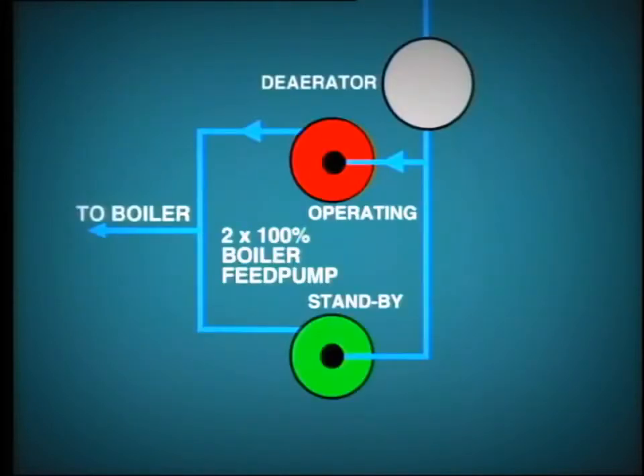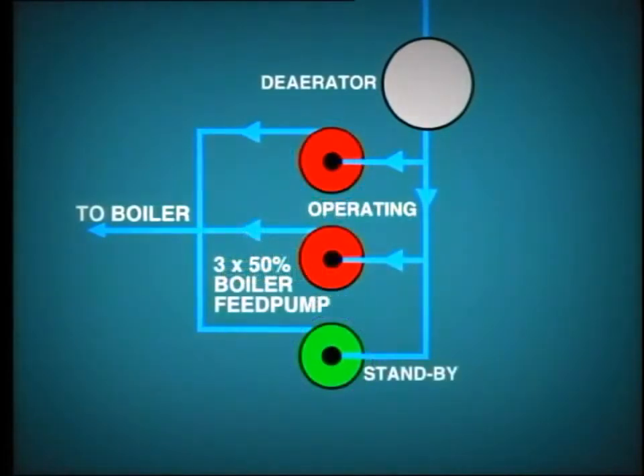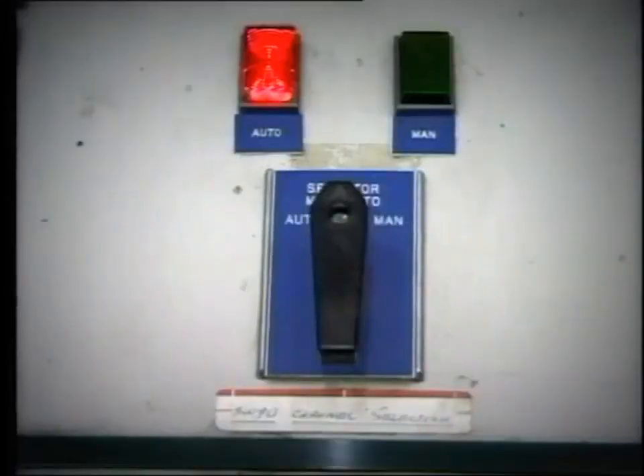In many power plants, two boiler feedwater pumps may be installed, providing 100% standby. An alternative to this arrangement is to provide three 50% pumps. The standby pump may be made available for automatic start in case of failure of the running pump and a decrease in feedwater pressure.